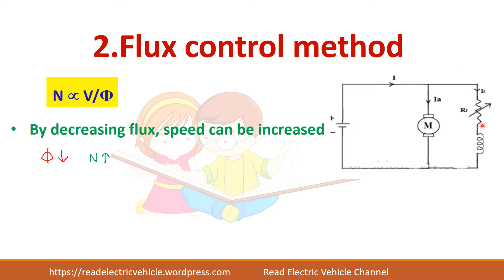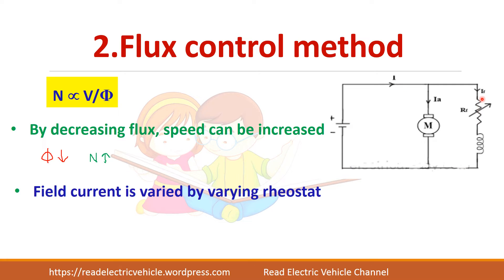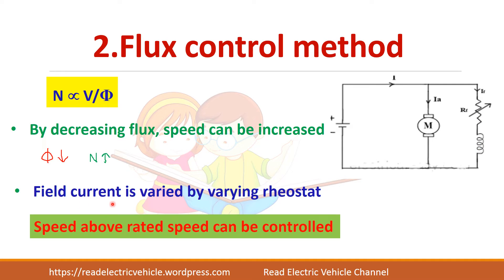Here also you have to note that a resistor is connected in series with the field winding. The total applied voltage remains the same, so you can only reduce the flux here — the field current is reduced. If the field current is reduced, speed will increase. So you can achieve speed control only above rated speed.